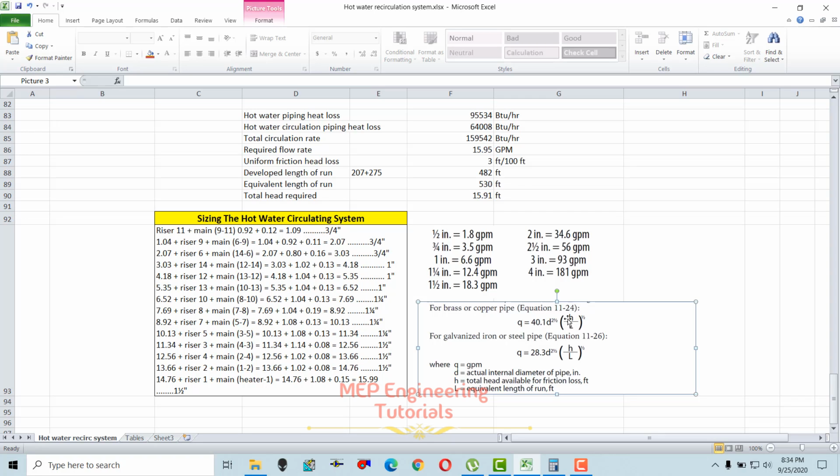So we have the H value, head, that is 16, and length, per unit length we have calculated here. And Q we also know, that is 16 GPM. If you know all the values, the thing remaining is D, that is the diameter for piping. So you can calculate it easily after putting in all the values.